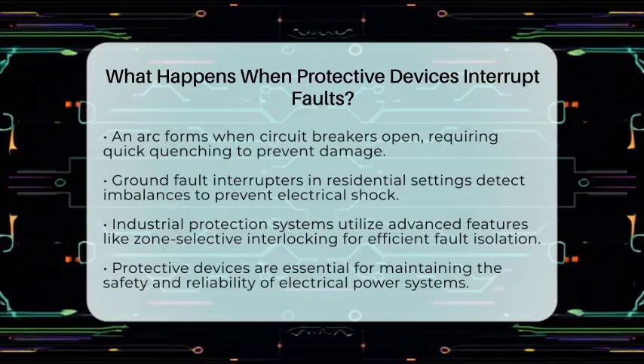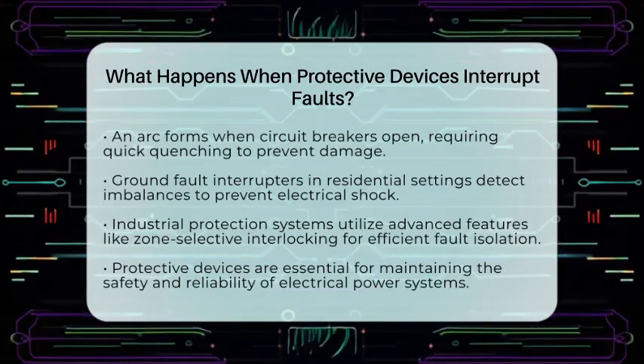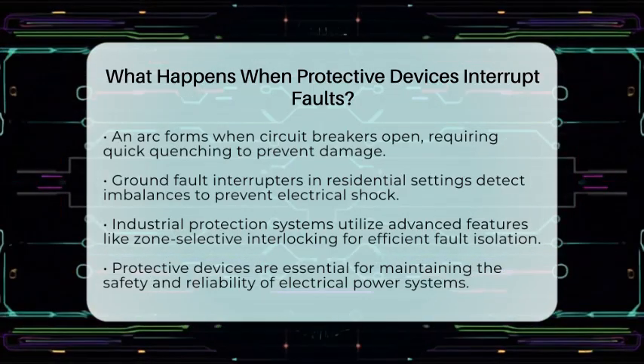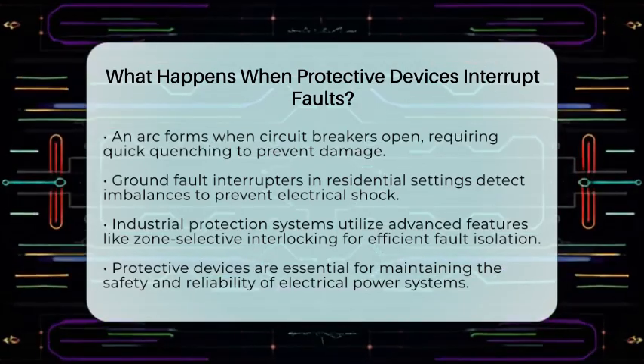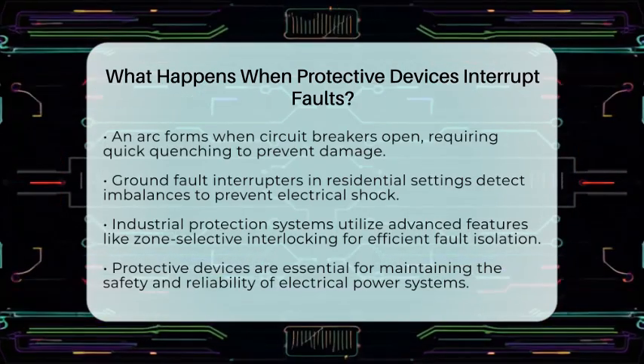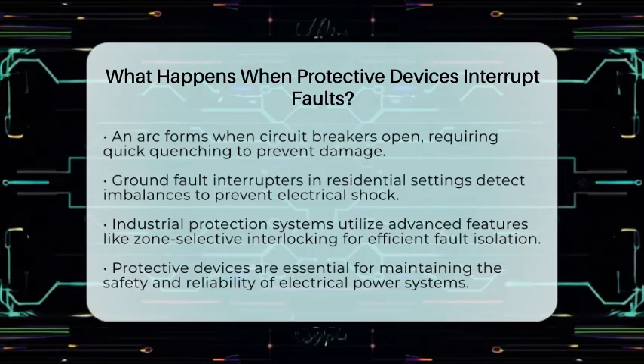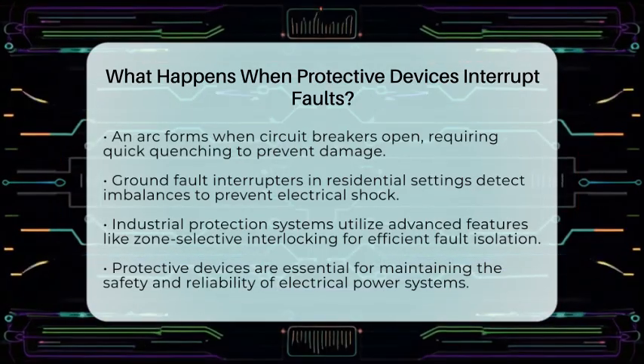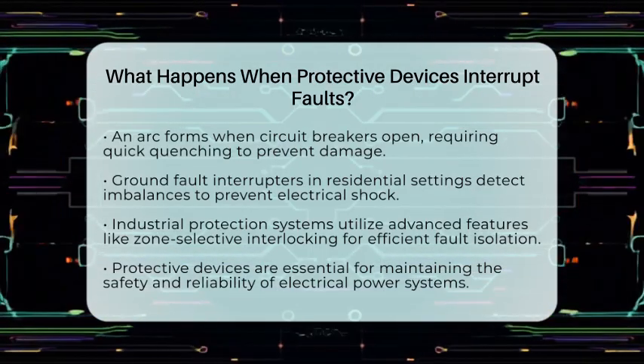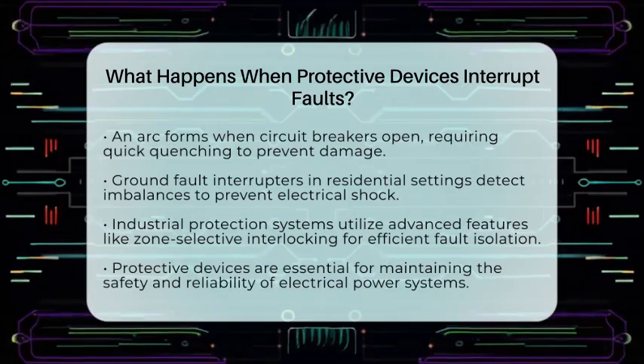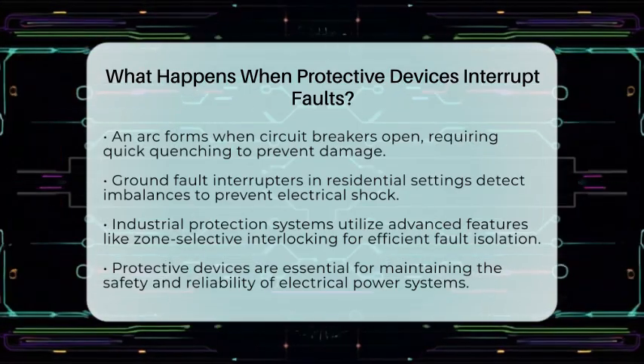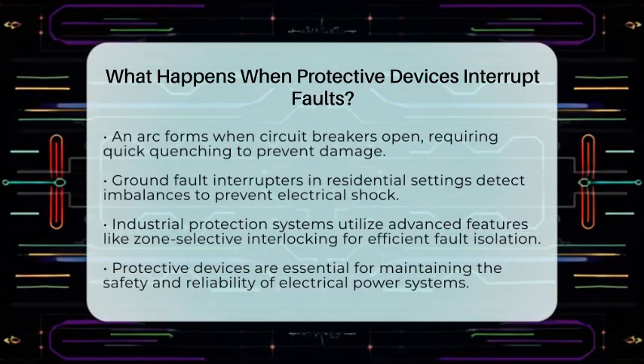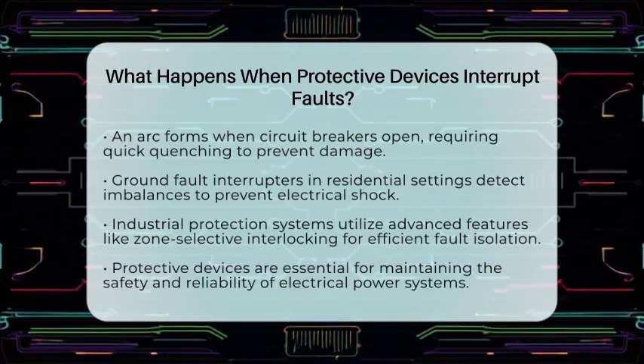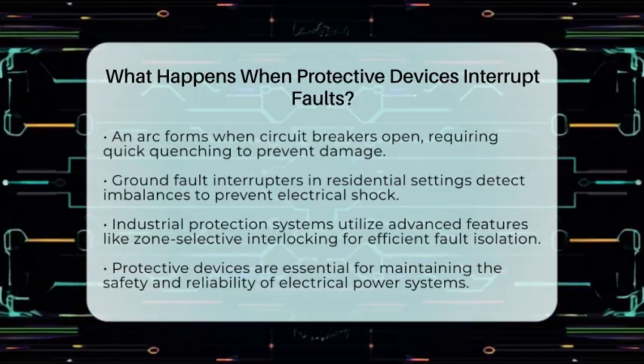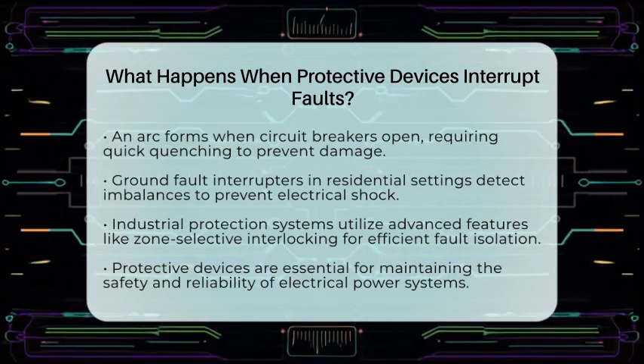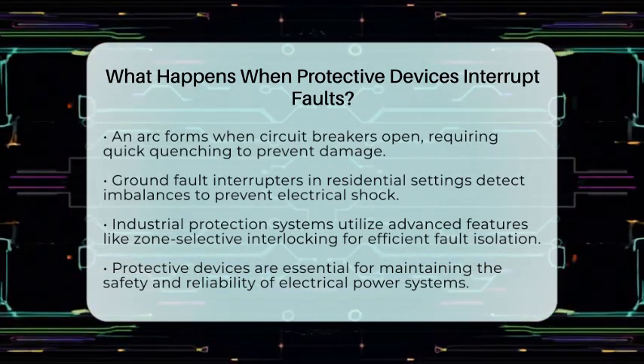For example, in a residential setting, a ground fault interrupter can detect imbalances in current flow and quickly disconnect the circuit if a ground fault occurs, preventing electrical shock. In industrial settings, more sophisticated protection systems are used to minimize downtime and protect expensive equipment. These systems often include zone-selective interlocking, allowing for the isolation of faulted sections without affecting the rest of the system.